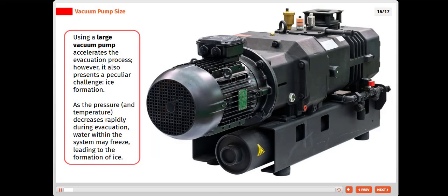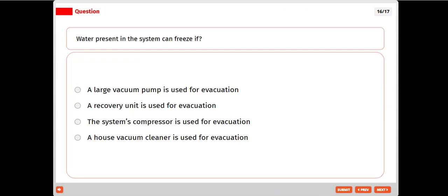Using a large vacuum pump accelerates the evacuation process. However, it also presents a peculiar challenge: ice formation. As the pressure and temperature decrease rapidly during evacuation, water within the system may freeze, leading to the formation of ice. Water present in the system can freeze if a large vacuum pump is used for evacuation. Yes, it can freeze.